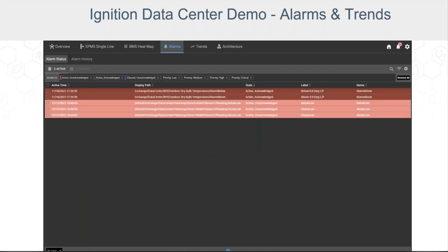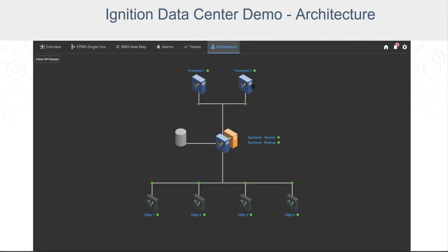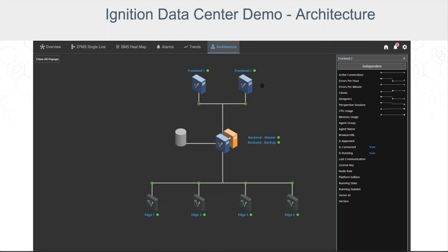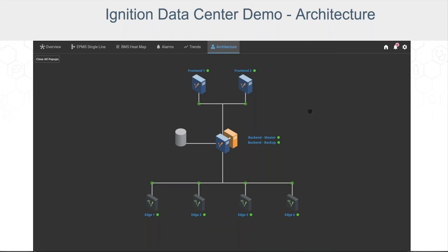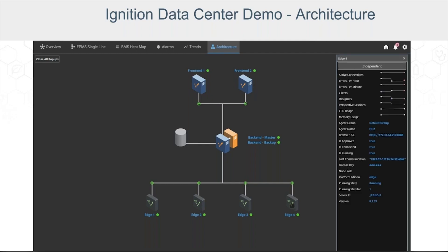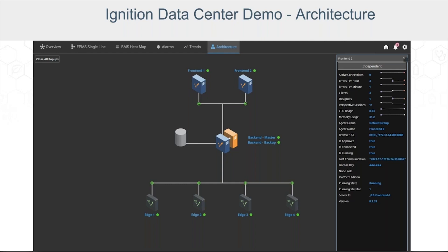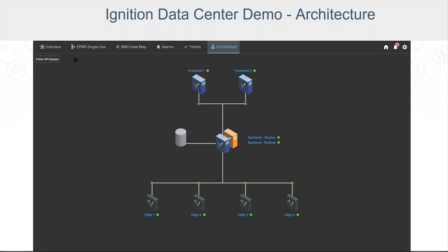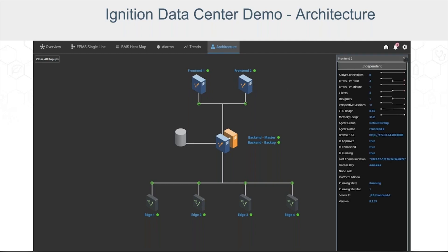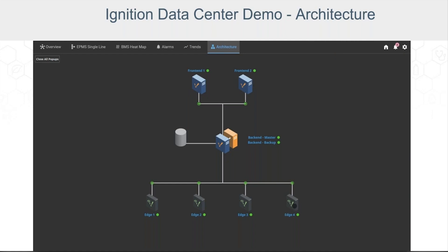Finally, let's take a look at the architecture screen. This view depicts the specific Ignition architecture for our data center demo — you can see two front-end servers hosting Perspective UI sessions connected to a back-end server for all of the tags, alarming, and historization. The back-end also has a redundant server as a standby in case the main back-end server temporarily goes down. The back-end server is also connected to a database to store history and connected to remote I/O via Ignition Edge gateways. You can click on any of these servers to get more detailed information on the health and status of both the Ignition gateway and the actual server it's running on.